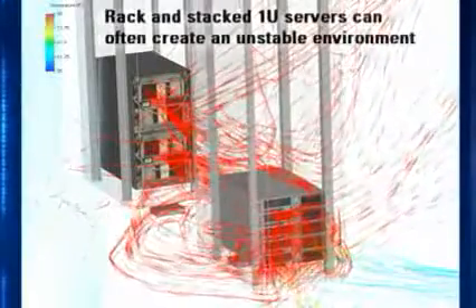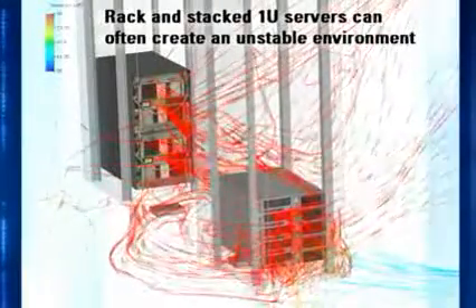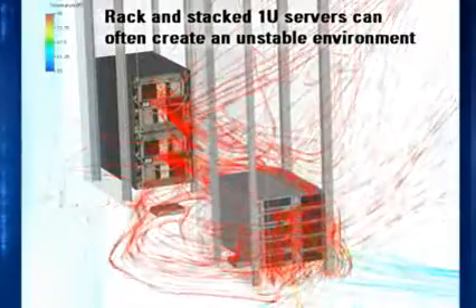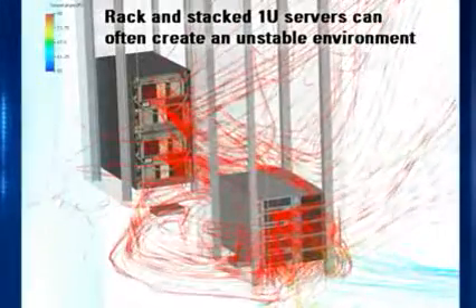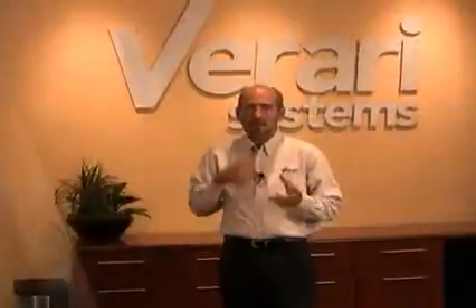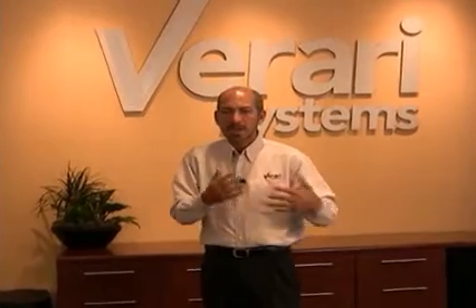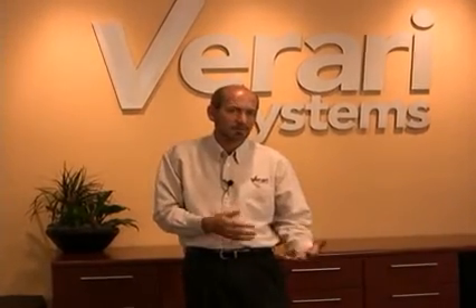Typically, when you rack and stack 1Us, you'll see a dramatic range in the amount of airflow that goes into the 1Us, with the ones near the bottom and the very top getting up to 40 and 50 CFMs of air, and the ones near the middle getting only 20 to 25 CFMs of air, due to the fact that you can't control the fan speeds based upon the volume that's going into the system, and you're just having to deal with whatever pressure is there and whatever air temperature is there.